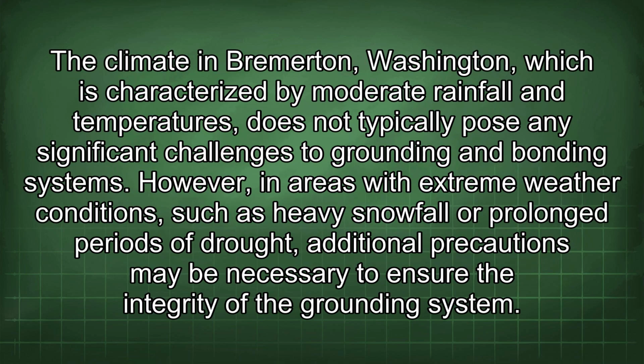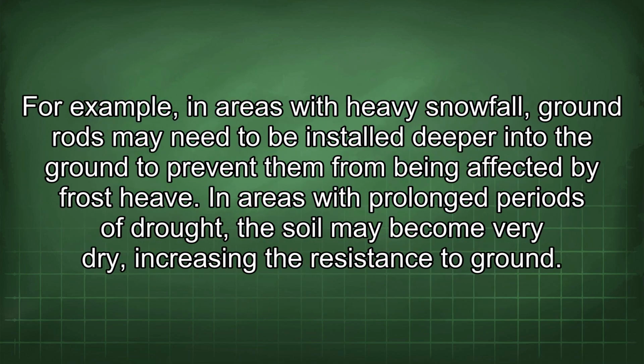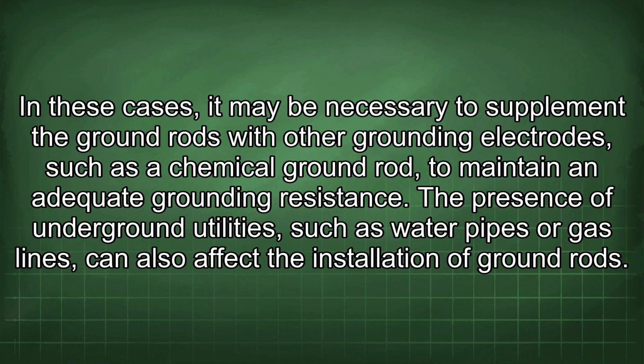The climate in Bremerton, Washington, which is characterized by moderate rainfall and temperatures, does not typically pose any significant challenges to grounding and bonding systems. However, in areas with extreme weather conditions, such as heavy snowfall or prolonged periods of drought, additional precautions may be necessary to ensure the integrity of the grounding system. For example, in areas with heavy snowfall, ground rods may need to be installed deeper into the ground to prevent them from being affected by frost heave. In areas with prolonged periods of drought, the soil may become very dry, increasing the resistance to ground. In these cases, it may be necessary to supplement the ground rods with other grounding electrodes, such as a chemical ground rod, to maintain an adequate grounding resistance.